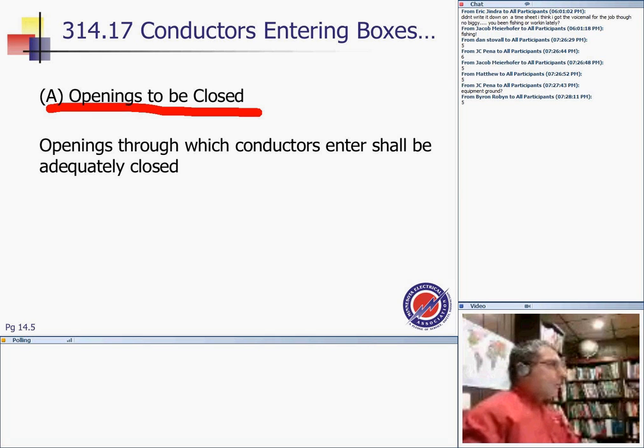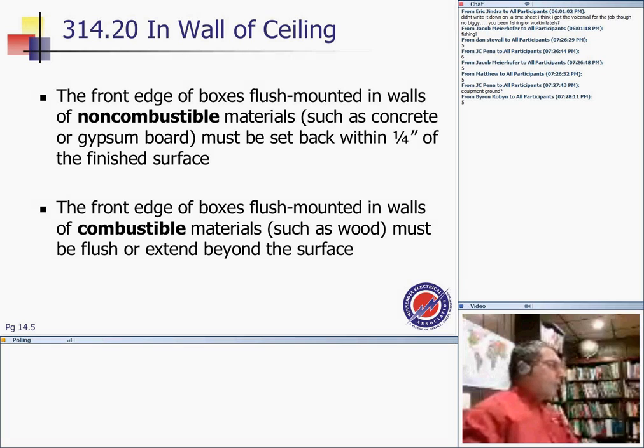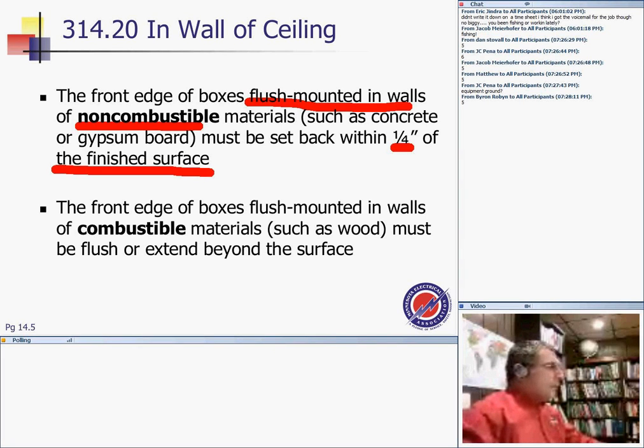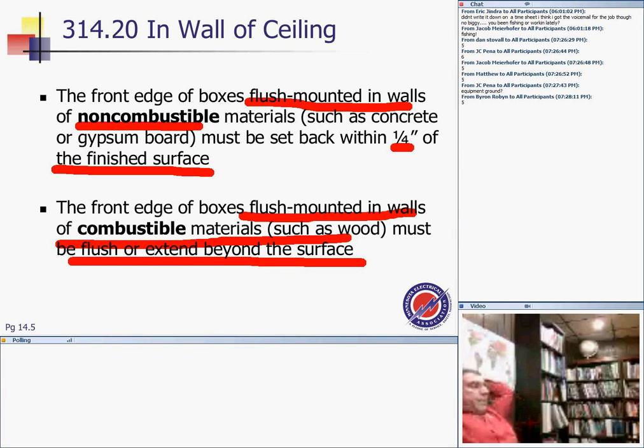Boxes must be closed in. We all know that because you don't want fire to escape and you don't want animals to walk right into your boxes. Walls or ceilings: does this sound familiar, you guys? If boxes are flush mounted in walls of non-combustible material, such as concrete, they must be set back no more than a quarter inch. If it's combustible material such as wood, the box must be flush or extend beyond the surface. But if it's non-combustible, you can set back up to a quarter inch.